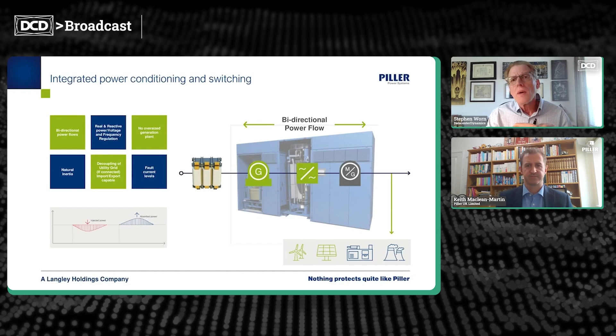The key to fully flexible power conditioning and stabilization is the bidirectional power flow technology that sits within the stabilization technology. This allows an equal amount of energy to be absorbed or delivered via the kinetic energy store, reacting to both power deficits and an excess of power as the supply and demand in the microgrid changes.